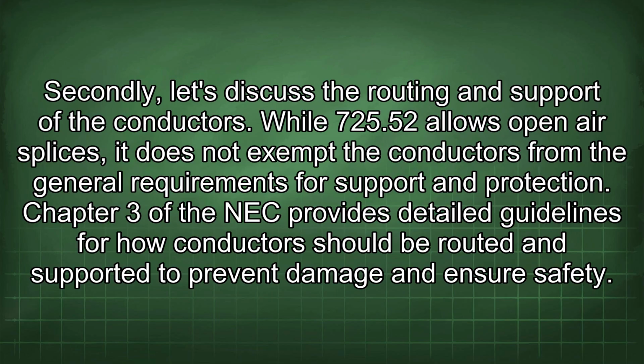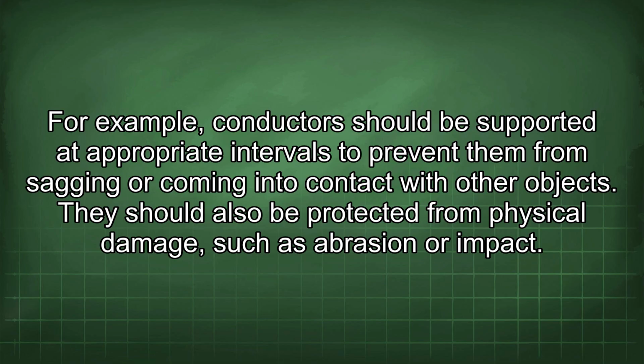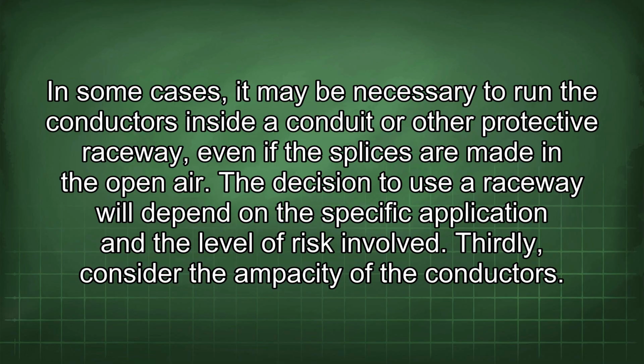Secondly, let's discuss the routing and support of the conductor. While 725.52 allows open-air splices, it does not exempt the conductors from the general requirements for support and protection. Chapter 3 of the NEC provides detailed guidelines for how conductors should be routed and supported to prevent damage and ensure safety. For example, conductors should be supported at appropriate intervals to prevent them from sagging or coming into contact with other objects. They should also be protected from physical damage such as abrasion or impact. In some cases, it may be necessary to run the conductors inside a conduit or other protective raceway, even if the splices are made in the open air. The decision to use a raceway will depend on the specific application and the level of risk involved.